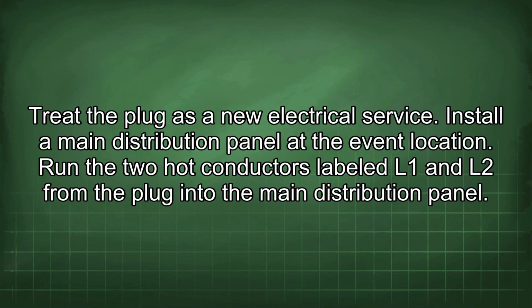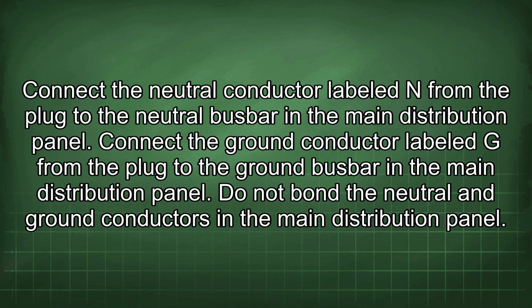Treat the plug as a new electrical service. Install a main distribution panel at the event location. Run the two hot conductors labeled L1 and L2 from the plug into the main distribution panel. Connect the neutral conductor labeled N from the plug to the neutral busbar in the main distribution panel.